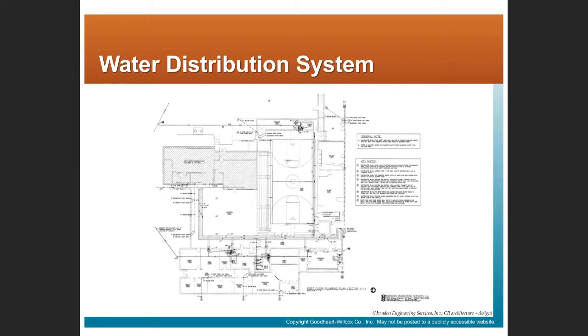In plan, looking right here, I see a couple different things happening. I see pipes labeled with a couple different symbols, and I don't see a key to this drawing, but over in there I see a 3/4 inch HWR, a 2-inch HW, which is hot water, a 2.5 inch CW, which is cold water, and a 2-inch G, which would be gas.